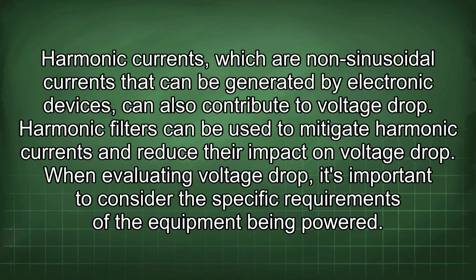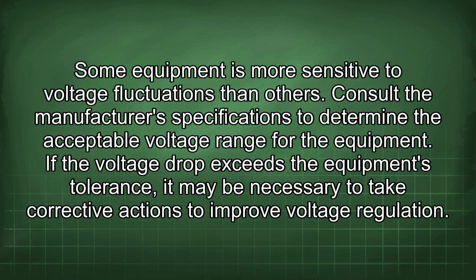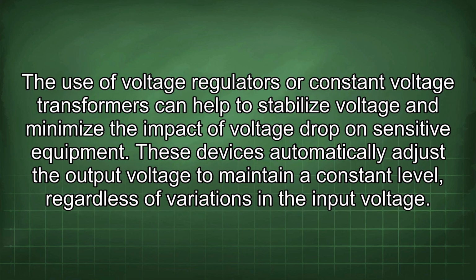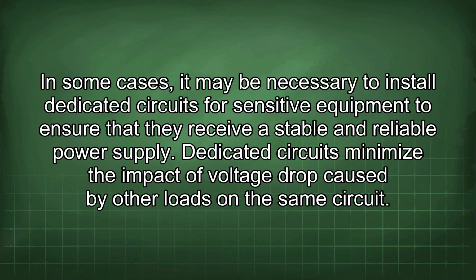When evaluating voltage drop, it's important to consider the specific requirements of the equipment being powered. Some equipment is more sensitive to voltage fluctuations than others. Consult the manufacturer's specifications to determine the acceptable voltage range for the equipment. If the voltage drop exceeds the equipment's tolerance, it may be necessary to take corrective actions to improve voltage regulation. The use of voltage regulators or constant voltage transformers can help to stabilize voltage and minimize the impact of voltage drop on sensitive equipment. These devices automatically adjust the output voltage to maintain a constant level, regardless of variations in the input voltage. In some cases, it may be necessary to install dedicated circuits for sensitive equipment to ensure that they receive a stable and reliable power supply.